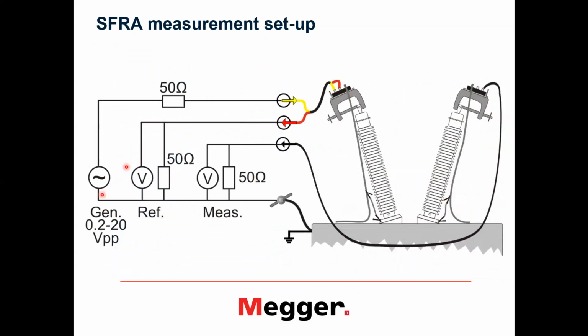We have a generator where we can output variable frequencies from several hertz to megahertz, and we apply this to one end of the transformer winding, and we measure this applied voltage as a reference voltage output. And then on the other side of the transformer winding, we measure what comes out. Out comes an attenuated signal, which we then relate to the generator output signal.